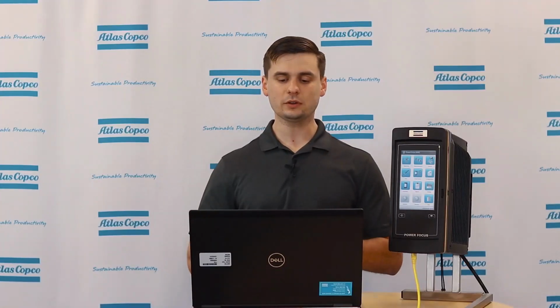So at this point, we've programmed our Fieldbus setup. Keep in mind a couple of things about the generic Fieldbus setup. We need to make sure that we're using the correct Fieldbus file type, whether it be an EDS file or a GSD file, whatever it may be. We want to make sure that we're using the correct one for the PowerFocus 6000. We also want to make sure that our generic settings, such as update interval, are set accordingly with the PLC. This was a very brief overview, but I hope it's been helpful in learning how to program the Fieldbus on the PowerFocus 6000 and getting you started with how you want to integrate these systems within your own PLCs.